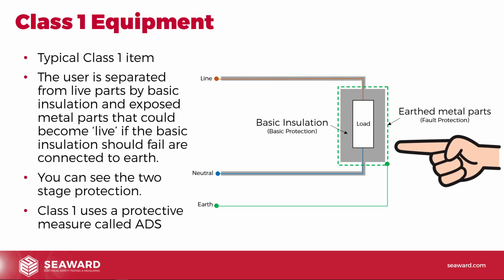And that's one of the hardest things we as PAT testers have to deal with: making the decision, is that earthed metalwork, is it unearthed metalwork, did the designer intend it to be earthed? Generally it is quite hard sometimes to make that evaluation. And obviously sometimes the only way you can work that out is to speak to the manufacturer, or maybe dismantle the equipment to a certain level, but we try and avoid that where possible, or maybe even do some continuity testing to try and work out which bits of the equipment are designed to be earthed for safety purposes and which bits are unearthed metalwork. But don't assume that on every piece of equipment everything should be earthed.